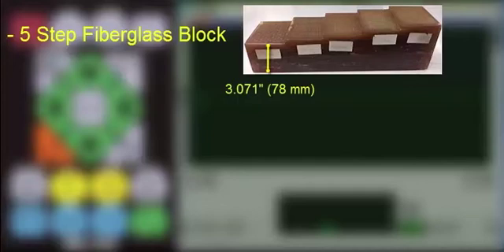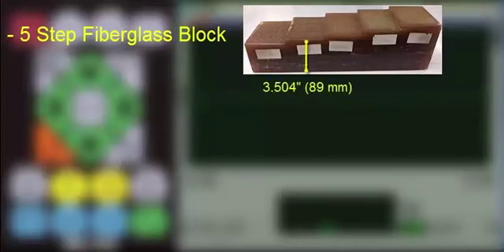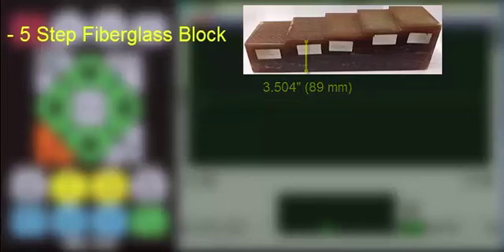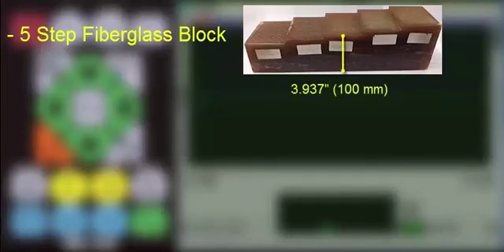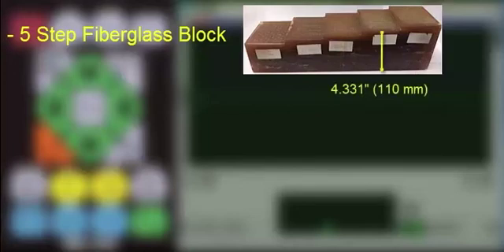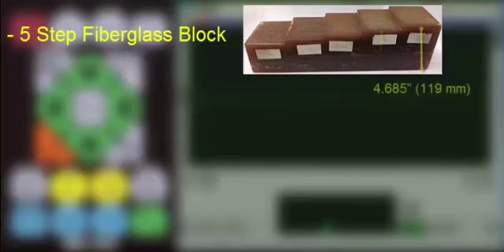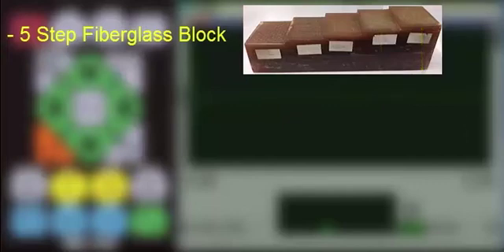In this demo, we will be measuring a 5-step fiberglass test block. The thickness of the steps are 3.071 inches or 78 millimeters, 3.50 inches or 89 millimeters, 3.937 inches or 100 millimeters, 4.331 inches or 110 millimeters, and 4.685 inches or 119 millimeters.